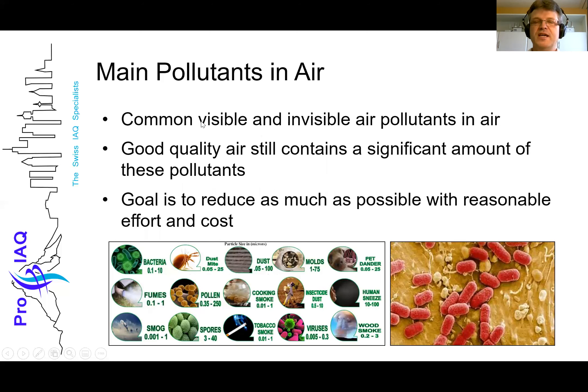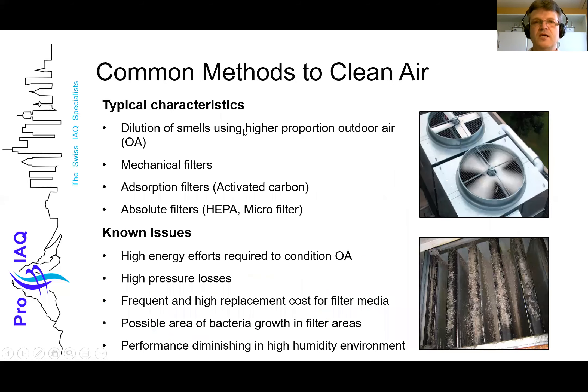The main pollutants of the air — as an engineer, I look from the practical side. We normally have issues with bacteria, tobacco smoke, viruses, and molds, and we have to solve these issues with the lowest possible cost and the highest possible outcome. The common methods to clean the air are by using dilution — to remove all scent smells and replace with fresh air — mechanical filters, adsorption filters like activated carbon, or absolute filters like HEPA filters.